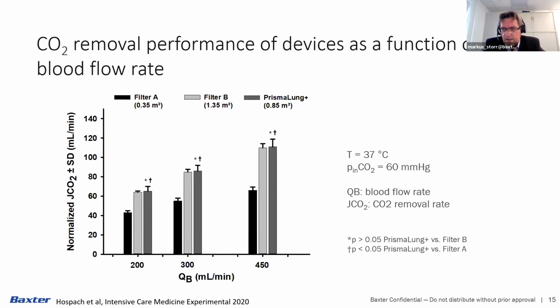The similarity in CO2 removal performance observed for PRISMALUNG Plus and the much larger filter in terms of surface area can be explained in that both membrane area and blood flow govern the rate of CO2 removal. However, at an increase in surface area above a certain threshold, we see limited impact on CO2 removal rate, since then the blood flow limits the CO2 removal rate.